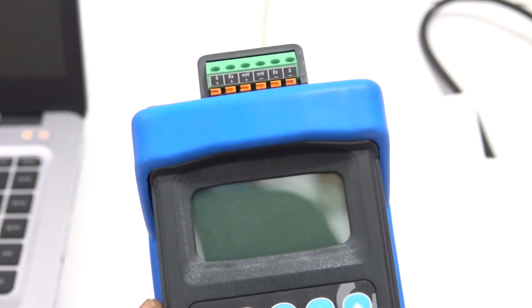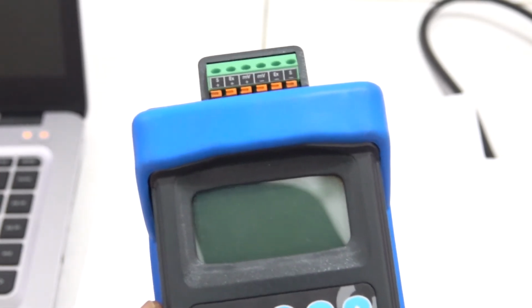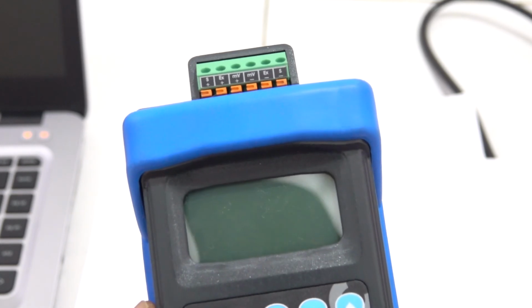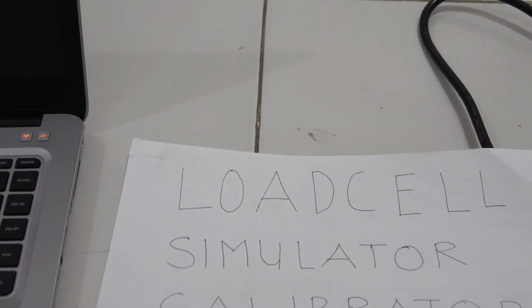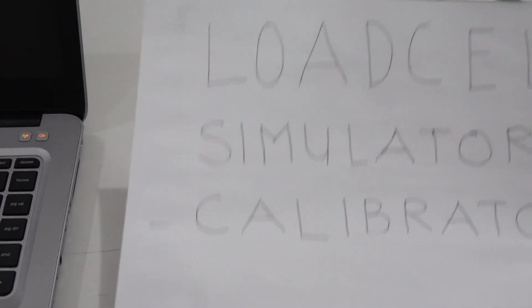You have to make sure that there is no overhang or no other loads on the system, and nothing that may obstruct the load cells, such as piping, etc. You can find in user manuals on the internet many guides on how to make weighing systems mechanically correct. So this is the video that explains the load cell simulator or calibrator equipment that you need.